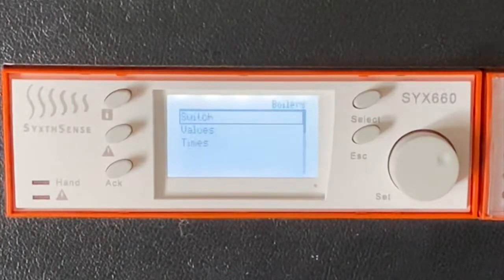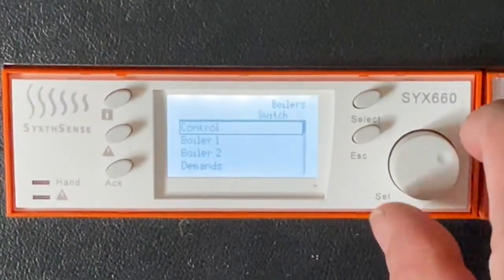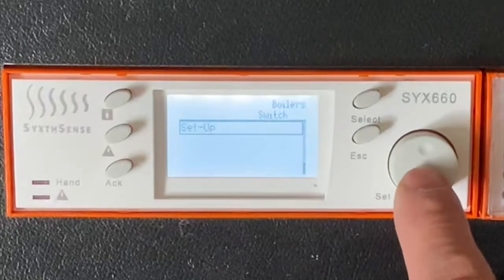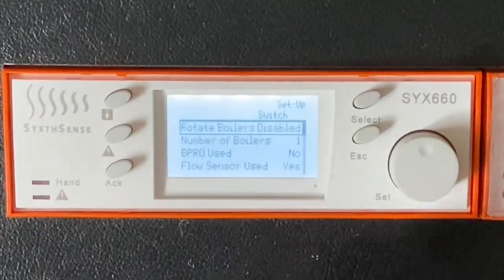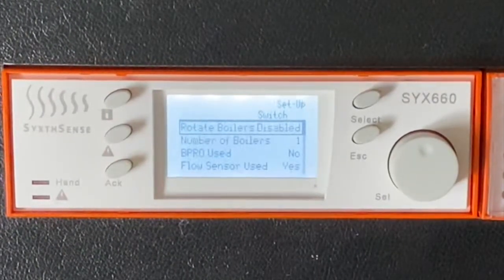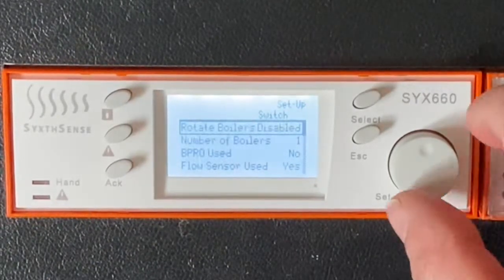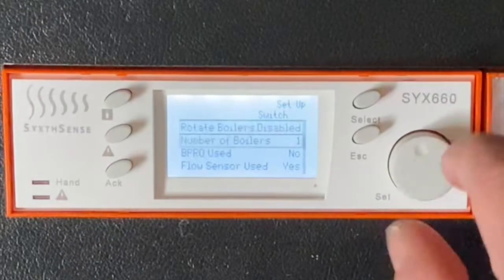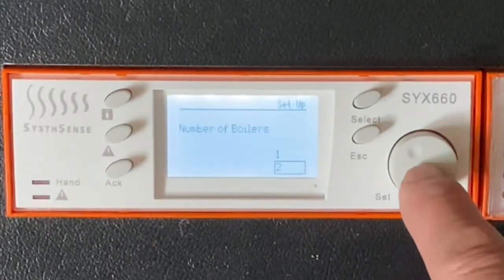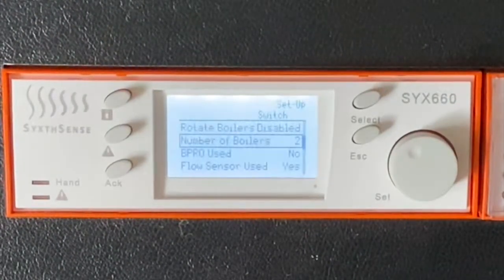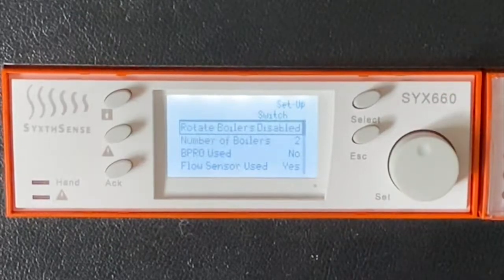Press set on boilers and I choose switch, I turn the wheel, I come down to setup, and now I can see rotate boilers, number of boilers, Boiler Pro used, and is the flow sensor used. So let's run through those. So number of boilers first, I'm going to set that to be 2 boilers. I can now set up whether I want those boilers to be rotated on a weekly basis.